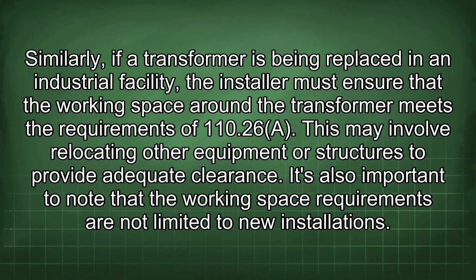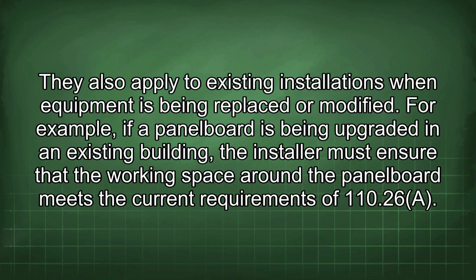Similarly, if a transformer is being replaced in an industrial facility, the installer must ensure that the working space around the transformer meets the requirements of 110.26(A). This may involve relocating other equipment or structures to provide adequate clearance. It's also important to note that the working space requirements are not limited to new installations. They also apply to existing installations when equipment is being replaced or modified.